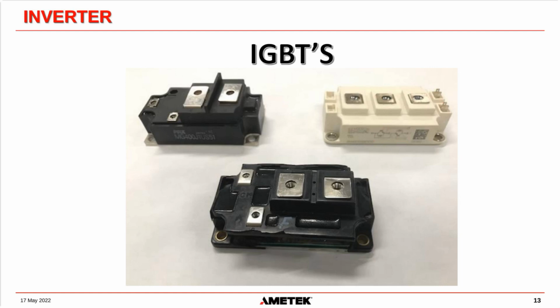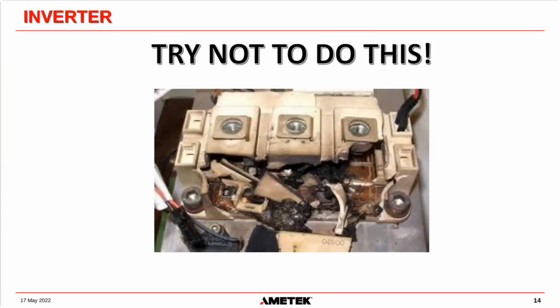Okay. And then the base of these IGBTs is flat metal, and it's heat conductive metal. There is no electrical connection between these terminals here or these terminals here down to the actual physical base of this. The physical base of an IGBT module like this is there to dissipate heat onto a heatsink. So these IGBTs will always be mounted flush to a heatsink using white non-electrically conductive heatsink compound. Okay, the heatsink compound is only there to transfer heat very easily. And this is what you should not do.